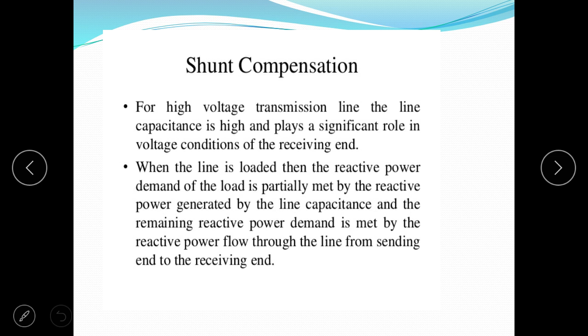So in shunt compensation, when load is high, a large reactive power flows from the sending end to the receiving end, resulting in a large voltage drop in the line. We know that due to heavy loading, current in the line increases, which creates a voltage drop in the line, due to which stability of the system reduces. So to improve the voltage at the receiving end, shunt capacitors may be connected at the receiving end to generate and feed reactive power to the load, so that reactive power flow through the line and consequently the voltage drop in the line is reduced.